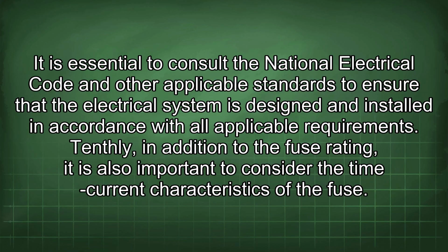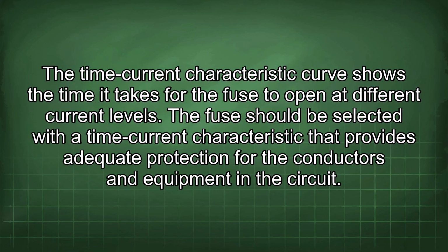Tenthly, in addition to the fuse rating, it is also important to consider the time current characteristics of the fuse. The time current characteristic curve shows the time it takes for the fuse to open at different current levels. The fuse should be selected with a time current characteristic that provides adequate protection for the conductors and equipment in the circuit.